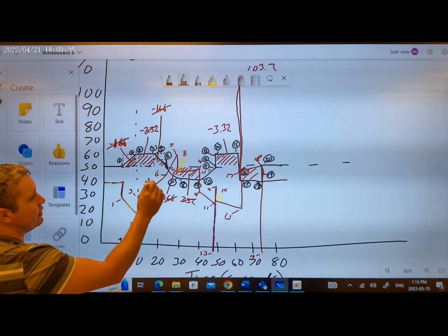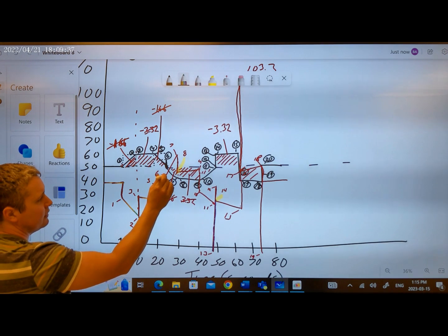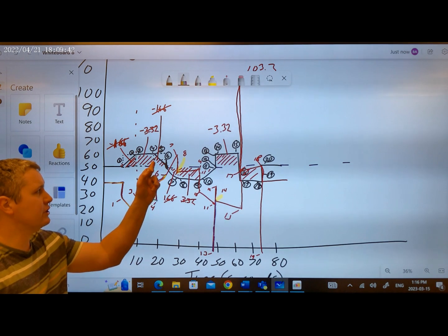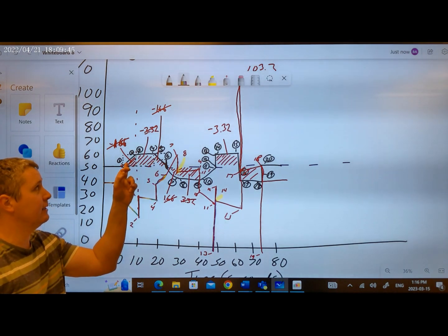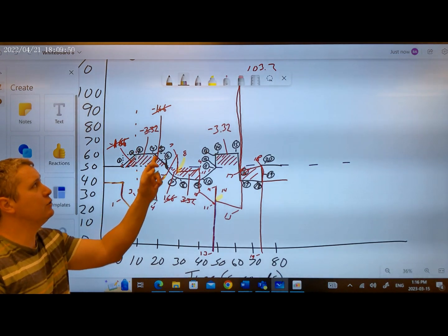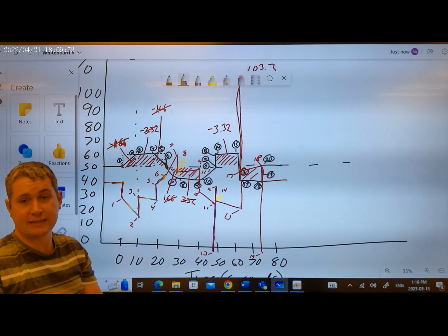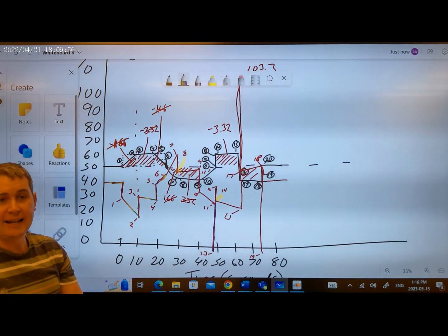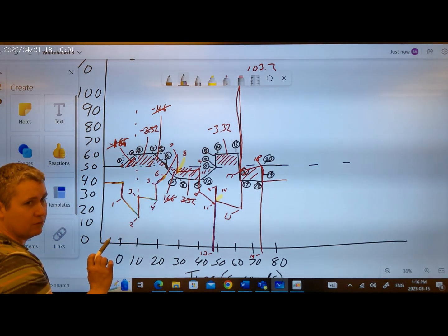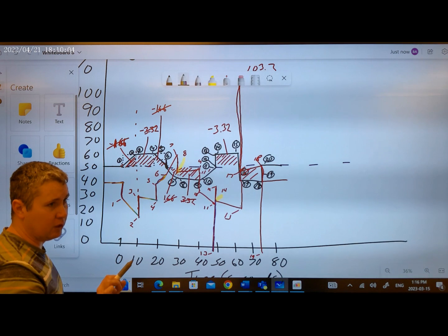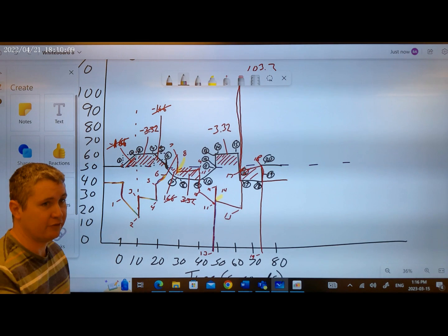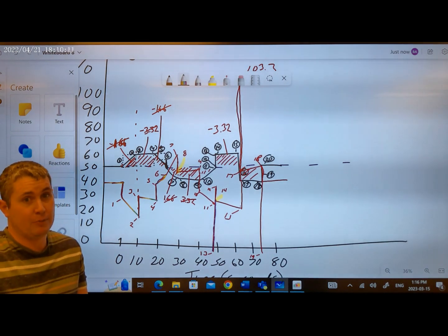Then over the course of the next 10 seconds, the ramp rate remains the same. However, we are still accumulating. We have already accumulated negative 1.66, negative 3.32, and now we need to accumulate another negative 1.66 of integral. At the same time, our proportional has gone from 10 to 0. So now our proportional error is 0. Instead of having a negative output, we have no proportional output.